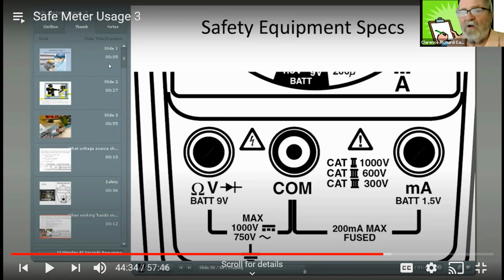Once you start diving into the 480 volts, you want to really make sure you know what you're doing. OSHA says if you're starting to expose yourself like that, we need protection, PPE. Now you're going to see a lot of electrical people working on controls that aren't wearing a lot of PPE, me included. I get to be a little bit like a cowboy sometimes. But if a short circuit happens and you're working on a motor starter that's got a 100 amp motor on it, if I short that out, there's going to be a lot of sparks. This is a true story.